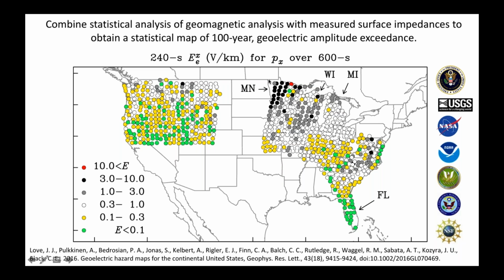If we were operating an electric power grid, we would have high voltage power lines which are stretched across large pieces of geography. So across Minnesota, if we were to integrate this geoelectric field across a length scale of 100 or maybe 1,000 kilometers, that would give us a voltage of thousands of volts, which would be uncontrolled voltage realized on a power grid system. And this seemingly small voltage, when integrated over the spatial dimension of a power grid, is why there are some substantial voltages that can be realized in a power grid system, which, like I say, are uncontrolled voltages. And that is the nature of the hazard for the power grid.